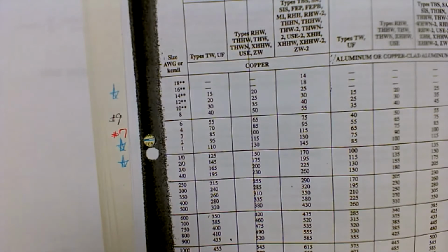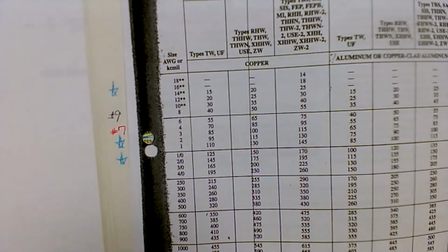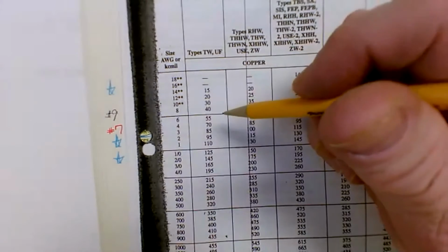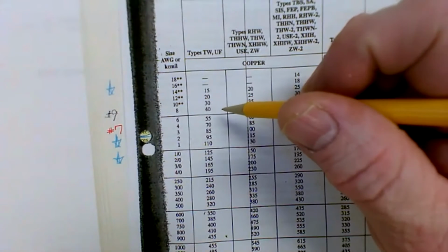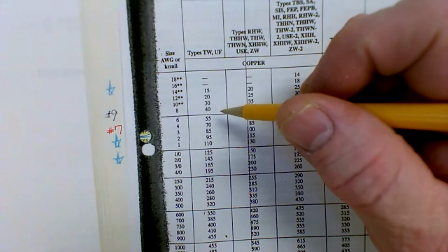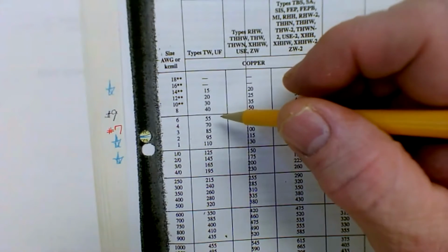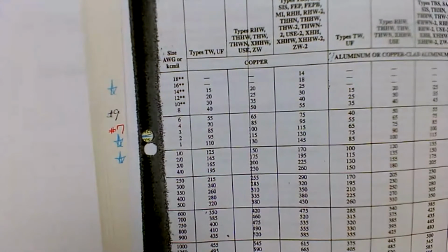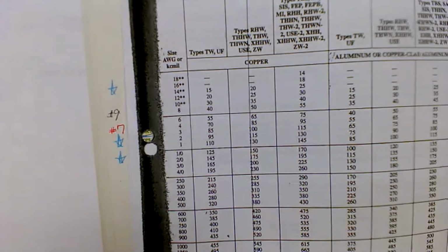That's what I'm thinking. So if you say, well, what's the solution? You would need to go to a larger wire size. Let's say you've got motors, and you derate, adjusting at 70% like we're saying for 8 conductors, and then you go back and ask whether 70% is enough for those fans. If it's not, then you've got to go up on wire size because you've got so many of them in the conduit.